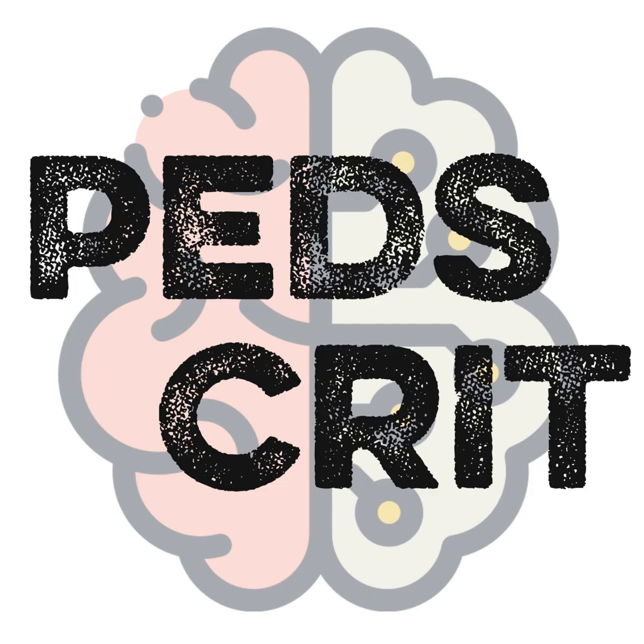Yes, in fact, we're measuring EDI and you're measuring all the other variables that you usually monitor during conventional ventilation. The other features that you should be aware of are the settings for NAVA. And in fact, it's quite simple, which does not mean that it's simple to set them, but it's simple because there are not a lot of settings. There's only the FiO2, of course, the PEEP level, which is the same PEEP level rationale as in conventional ventilation. And you have the NAVA level.